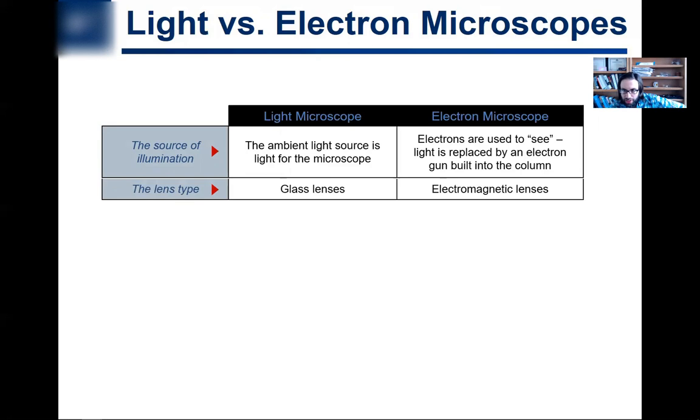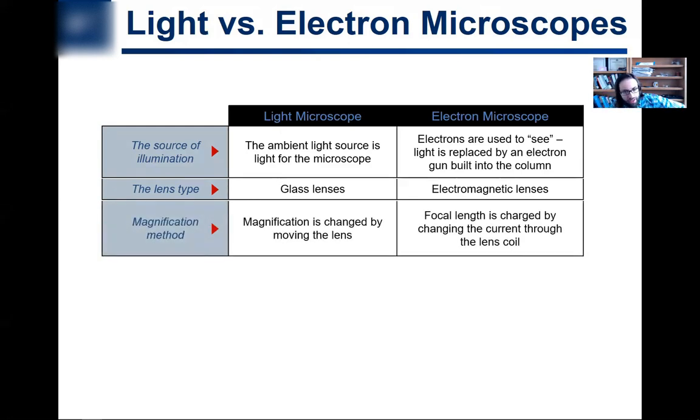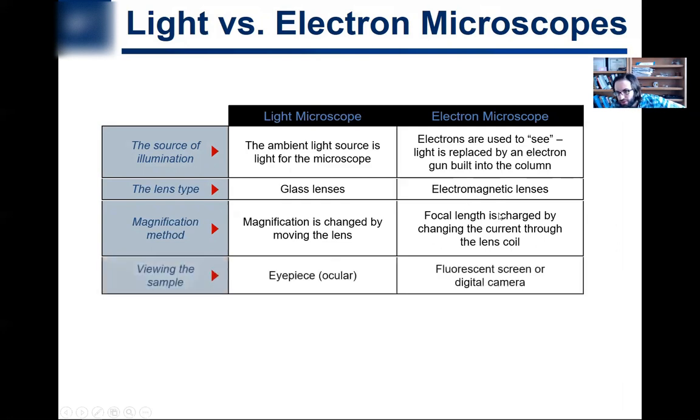In a light microscope, lenses are typically made out of polished glass. In an electron microscope you can't use glass - you have to use an electromagnetic lens, so you're basically bending electrons with magnets. How do you get magnification in a light microscope? Magnification is changed by moving the lens up and down. In an electron microscope the focal length is changed by changing the current in the coils of the magnet electromagnets. Very similar principles, basic principles.